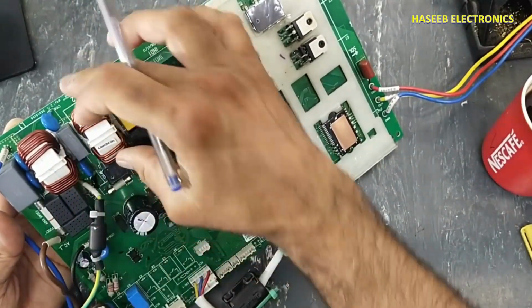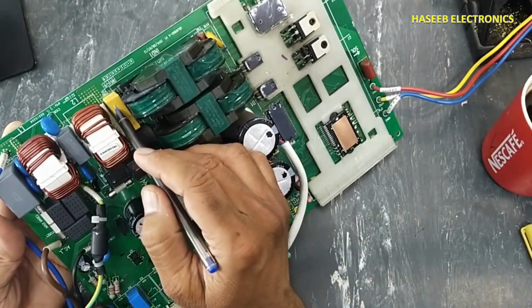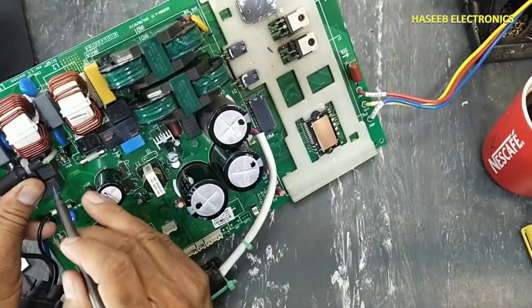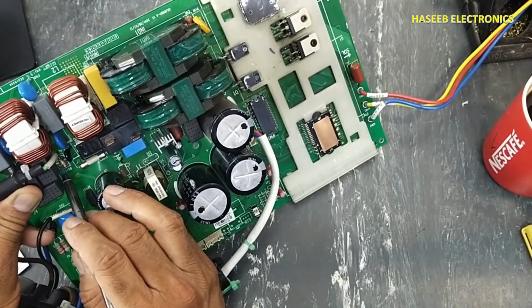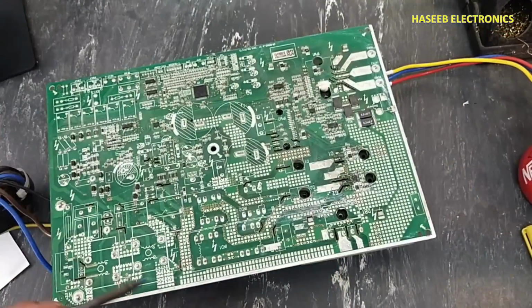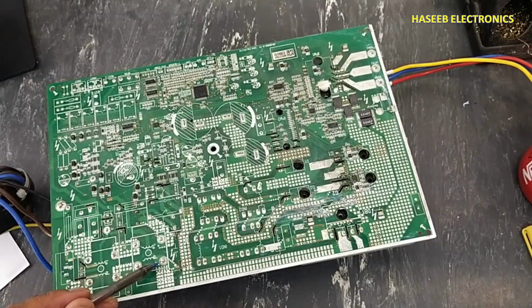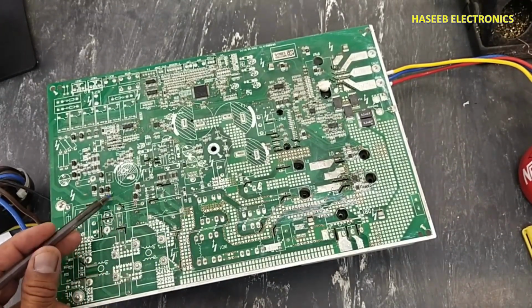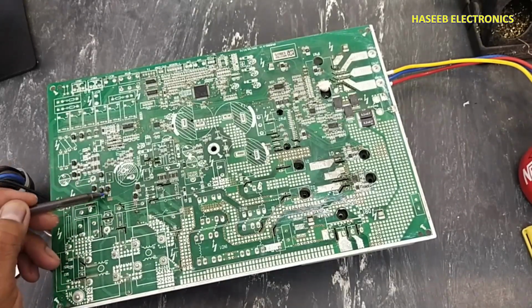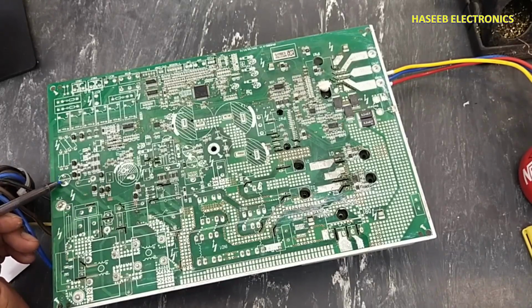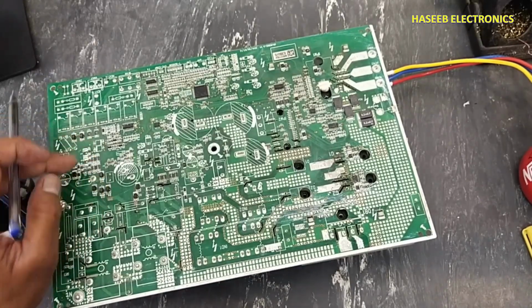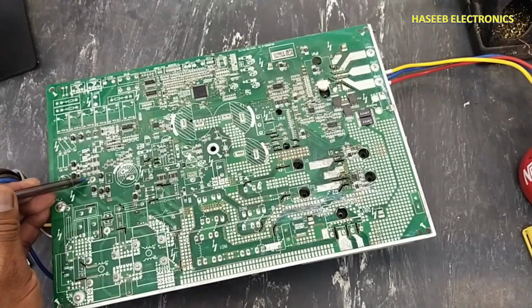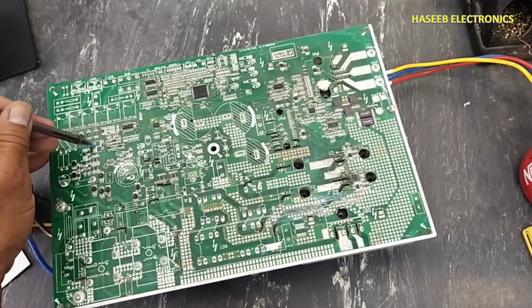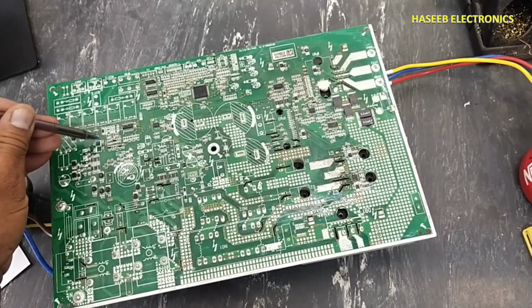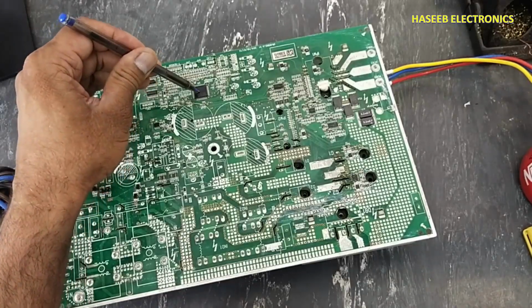Fuse, class X capacitor, first stage filter, class X capacitor, second stage dual line filter. Then we have this capacitor, that is also a class X capacitor, and here is the lightning arrestor. It is also connected in parallel. Then if you see this point, this is the common line. The common line reaches here, then it reaches this rectifier set, and we have a capacitor here to provide the voltage for the communication line. 2 optocouplers are here, communication wire here. All the communication data will be received and transmitted at this stage, and it will be communicated to the microcontroller.